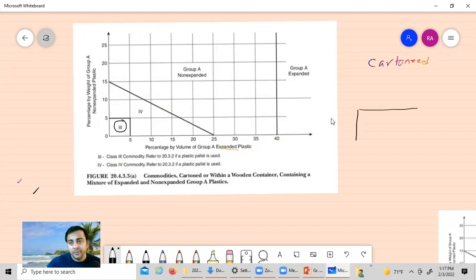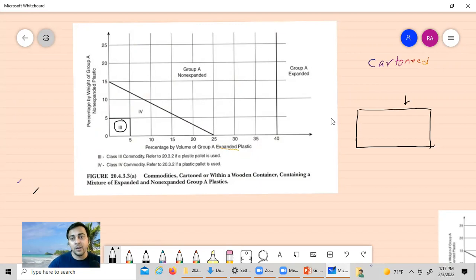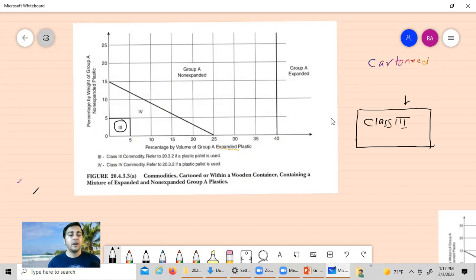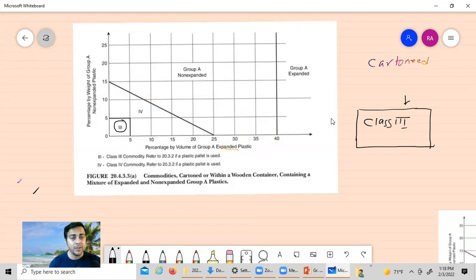To summarize simply: suppose this is a warehouse and you receive inputs from the client or owner about the products they are going to keep. You determine the commodity class and based on that you design your sprinkler system — pipe sizing, water requirement, pump and supply. In Class III commodities, you can keep around 5% by volume of Group A expanded plastic and 5% by weight of Group A non-expanded plastic.